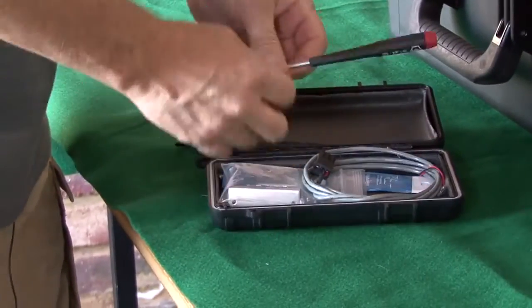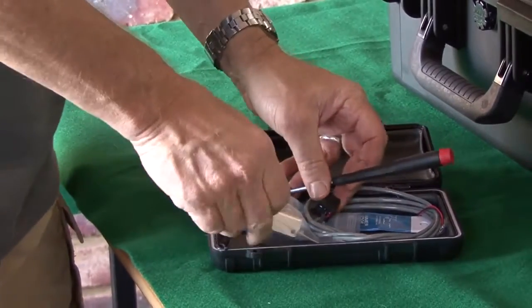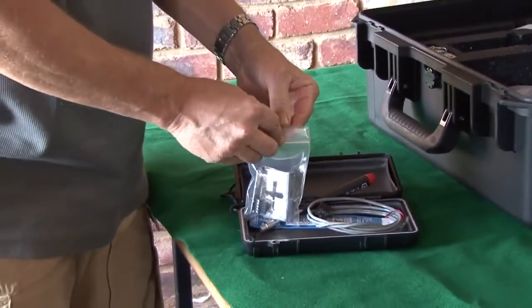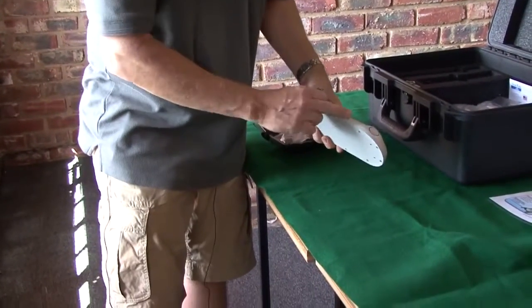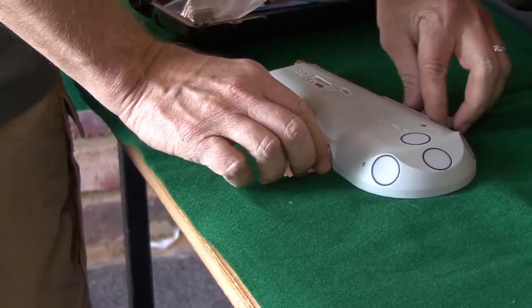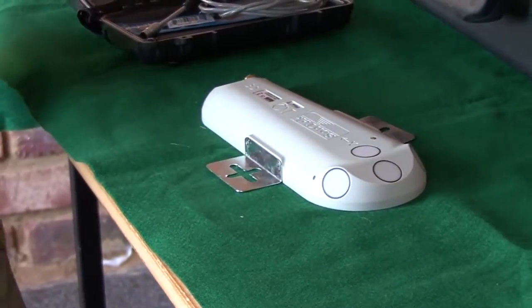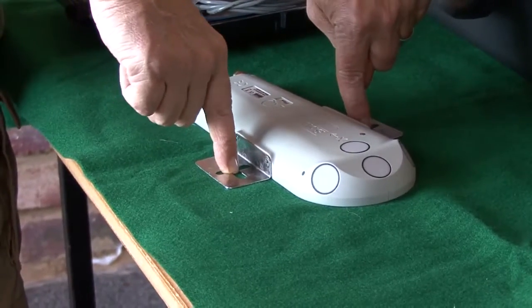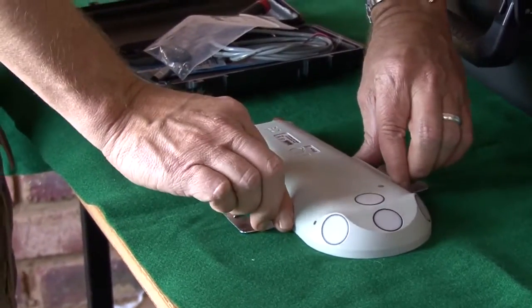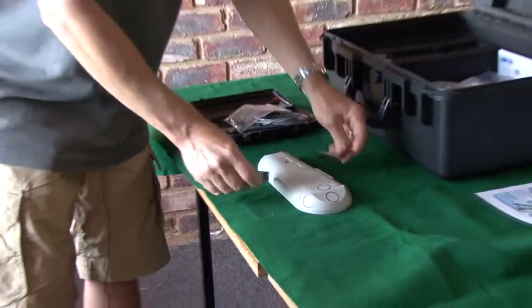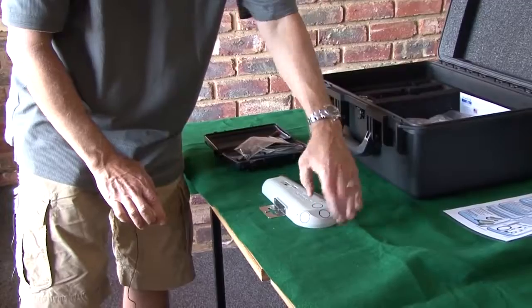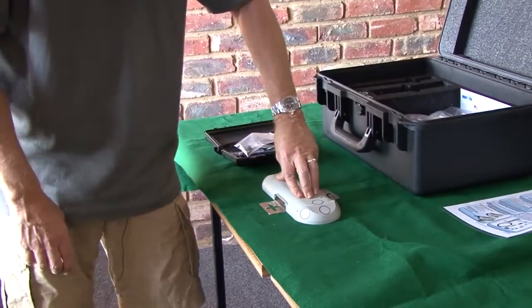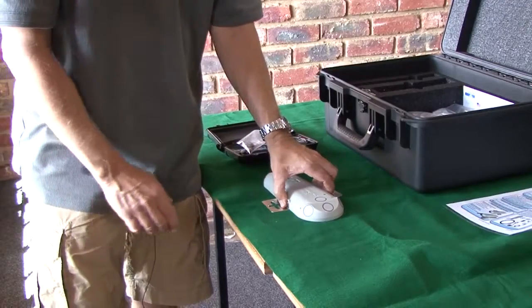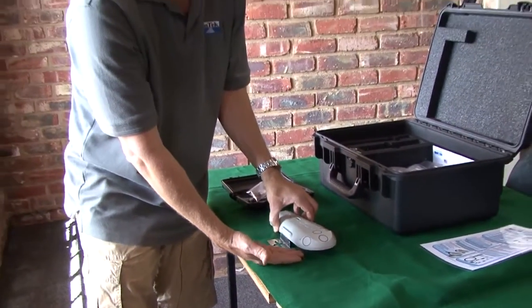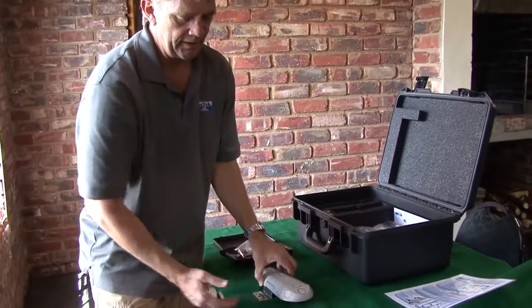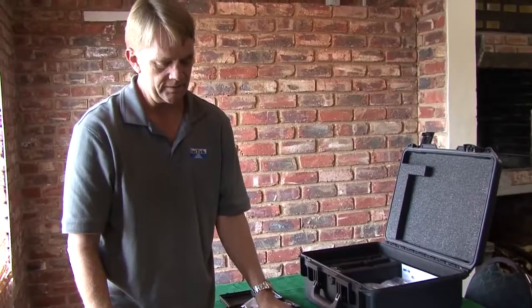Inside the toolbox, there's a little bit of hardware, a drill bit, some mounting brackets. I'll just take a minute to show you these real quick. The mounting brackets are designed, you can see there's little holes there. We can screw those in, and the hardware is there. In this case, you would drill a hole into the channel bottom or into your mount, and then you can mount it and align your IQ that way. So these brackets are here. We recommend that you mount the transducer or the housing as close as you can to the bed, especially if you're in shallow conditions, and try to minimize the amount of mount or anything you might have under it. Again, that's in really shallow water applications.